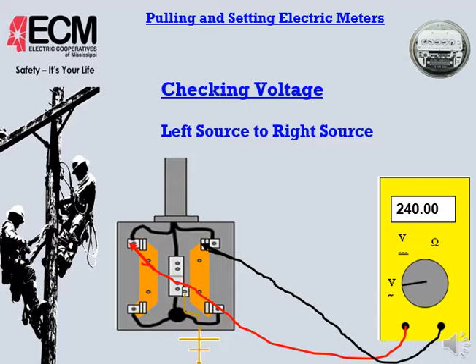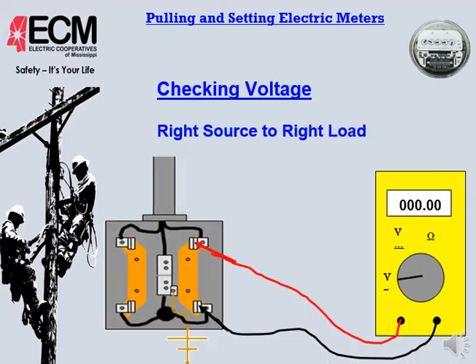Now, if you're getting to this point and you're not going any further, and you're setting a meter at this point, then you're taking a big chance. It's a gamble. A lot of cases we have a problem with a meter or a meter base. It's going to be on the consumer side, not on the source side. So if you're going to this point and setting a meter, you're skipping a lot of steps and taking a big chance.